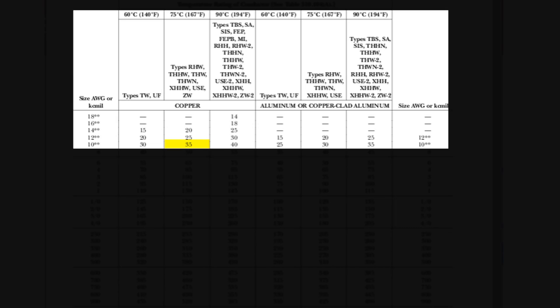Some THHN wire is actually rated at 90 degree Celsius. I'm not regularly looking at the wire that we have on our truck as far as the temperature rating, but if you want to, you can grab a roll of wire off the truck or look at one in an electrical supply house and you'll see these ratings listed on there. The question is, why do we often say that it's 30? So number 10 wire at 60 degrees Celsius insulation is 30, at 75 degrees 35, and at 90 degree it's 40, but we often say that it's 30.